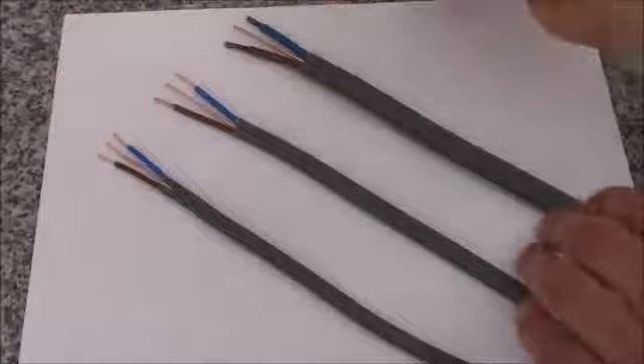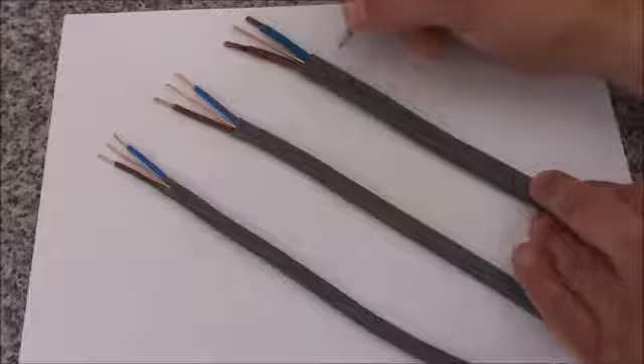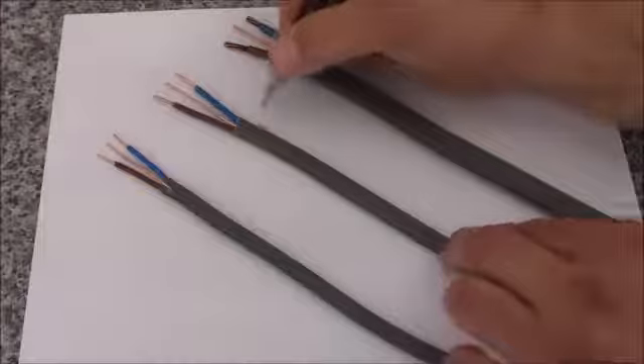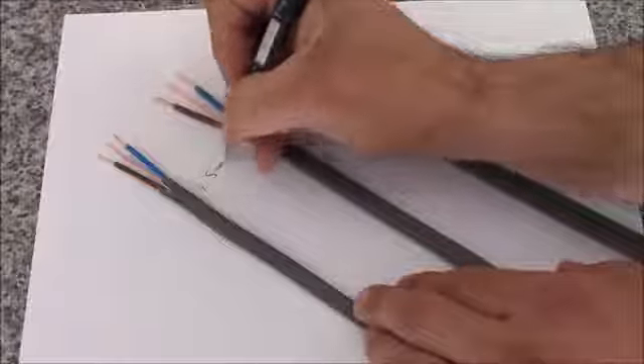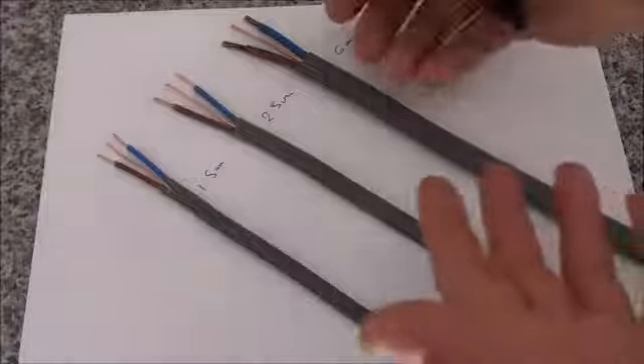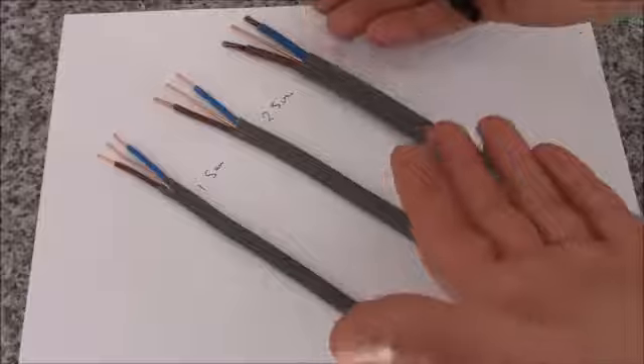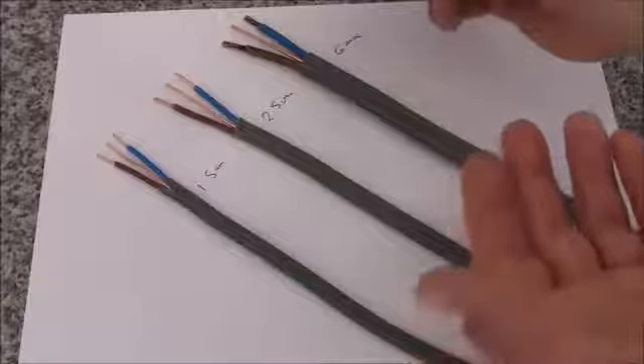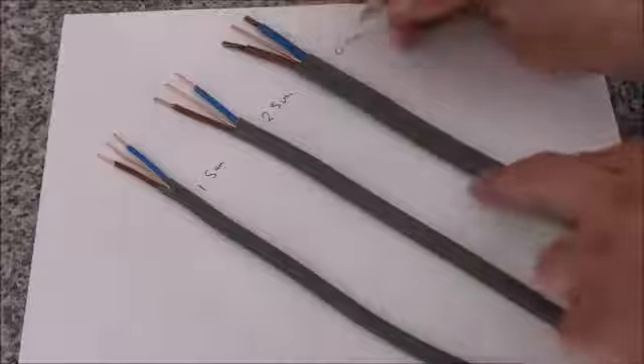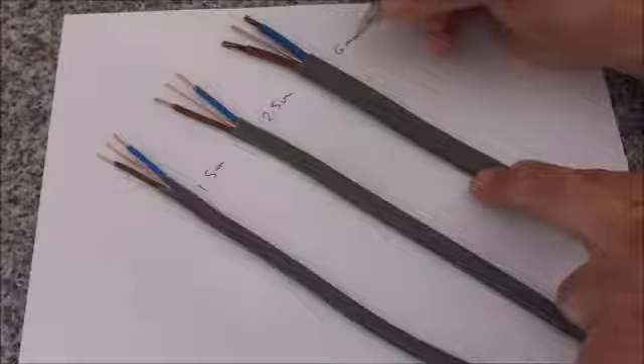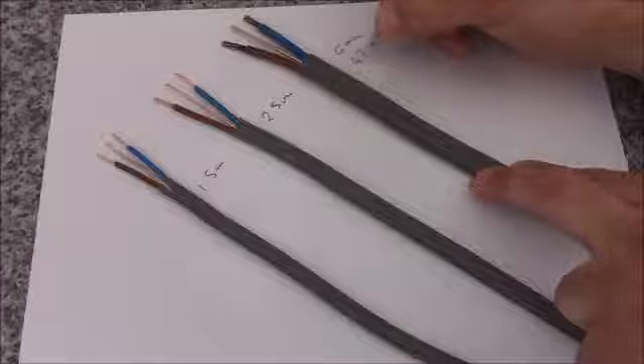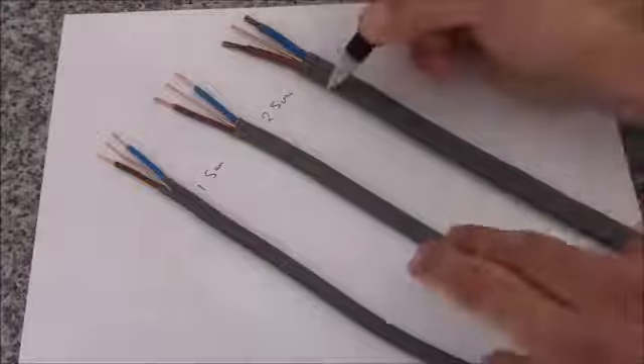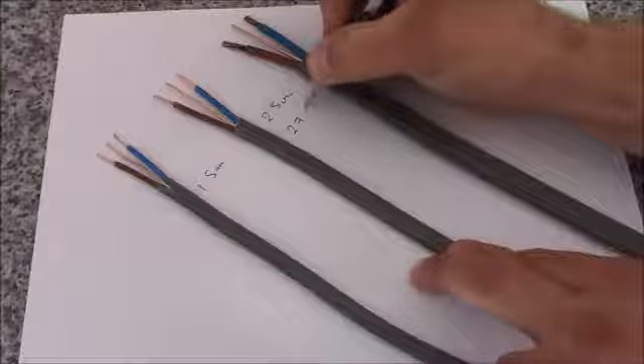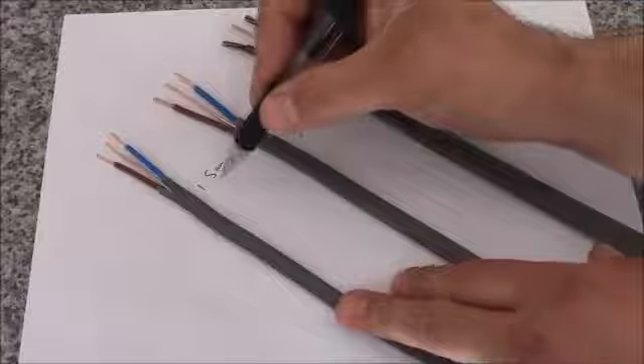So I've got here 3 cables, each a different size. This one is 6 millimeters, this one is 2.5 millimeters, and this one is 1.5 millimeters. And each cable has its own rating, depending on the size. This is called current carrying capacity. For example, the thick one, the 6 millimeter cable, has a current carrying capacity of 47 amps. We measure this in amps. The 2.5 is 27 amps, and the 1.5 is 20 amps.